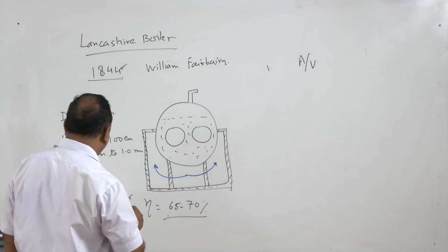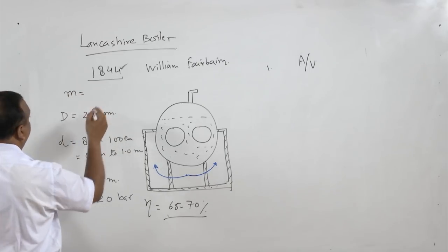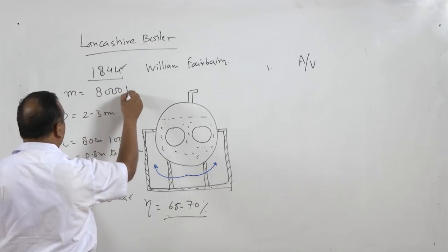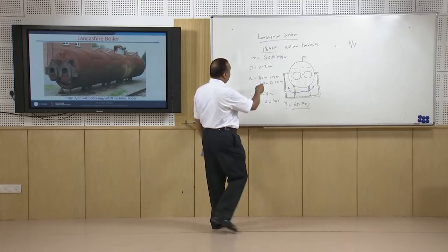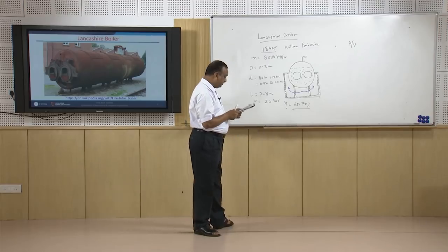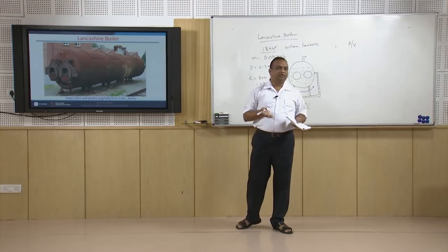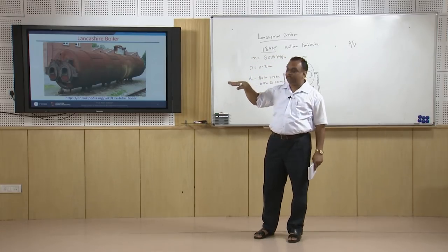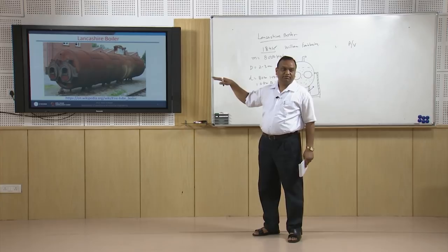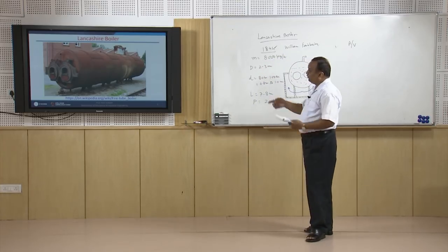The steam generation rate is also important in the boiler. Steam generation rate is approximately 8000 kg per hour. So 8000 kg per hour of steam can be generated in this boiler at 20 bar pressure. It is a stationary boiler because brick work has to be done. Classification-wise it is a stationary, horizontal boiler because the shell is in the horizontal direction.